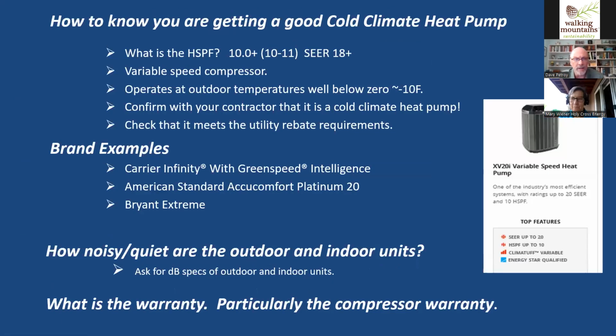So the number one priority is, how do you know you're getting a cold climate heat pump? We talked about heating season performance factor—most of the manufacturers' good cold climate heat pumps have an HSPF of 10 plus and SEER of 18 plus. With those numbers, there's a 90% chance it's a cold climate heat pump. It also has to have a variable speed compressor—without that, it's really not a cold climate heat pump.